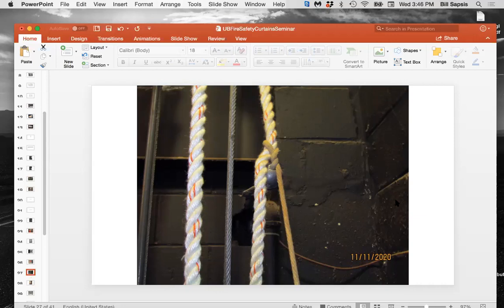Going back, Kino asks about recommendations regarding flame testing. A fire marshal should not be testing, you're talking about your stage curtains now. You're not talking about your fire curtain, because that's not something you can test without destroying it. But NFPA 701 small scale, the revised standard, which was revised 6 or 7 years ago, is the standard that is used to test stage curtains. And your fire marshal can do it if they are trained to do it. Most fire marshals are not.